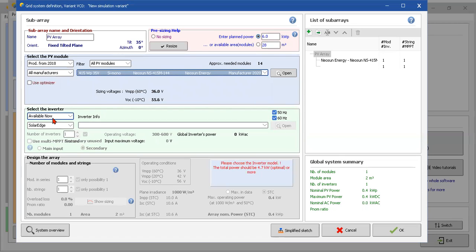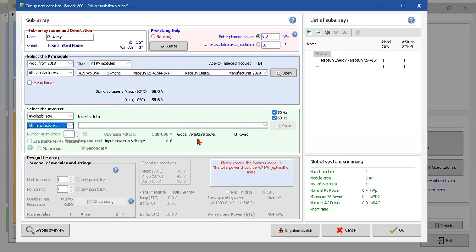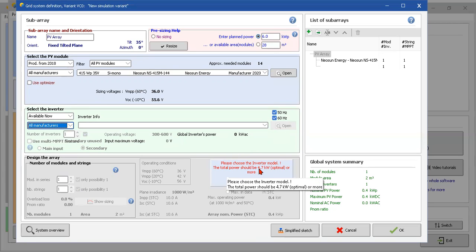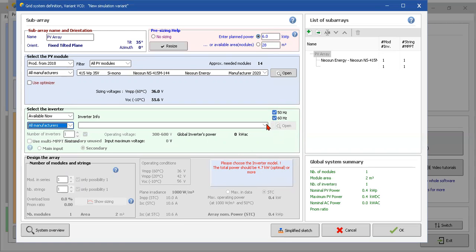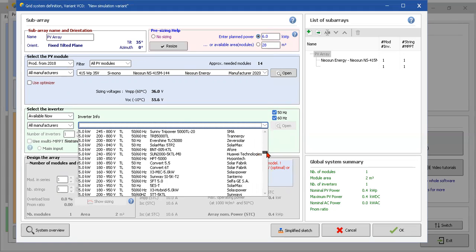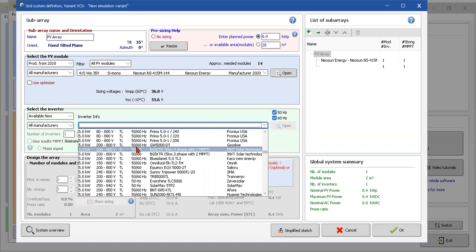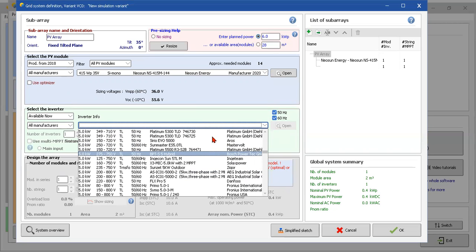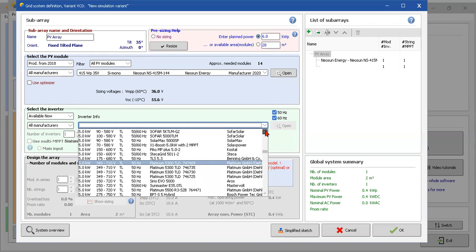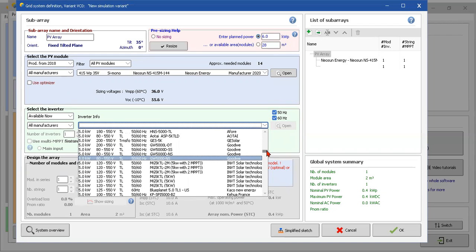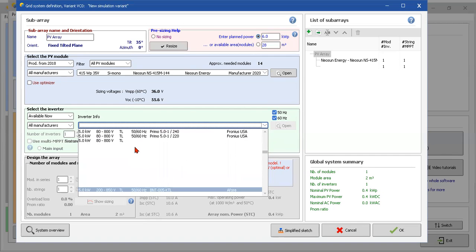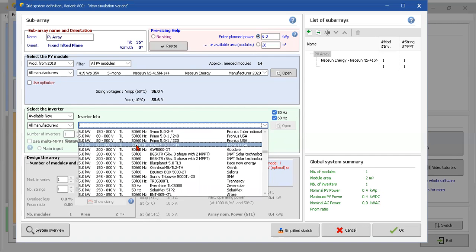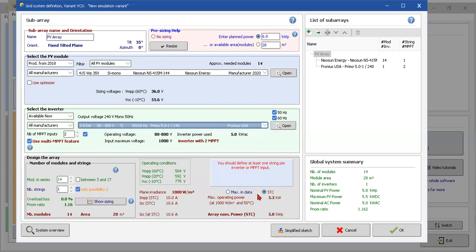Okay, inverter, manufacturer. So here the system said to you, please select an inverter that the power should be 4.7 kilowatts or more. This is gonna be the optimal, so we are not going to waste money in a bigger inverter. So let's see, 4.7 doesn't exist, I guess, not in the system.